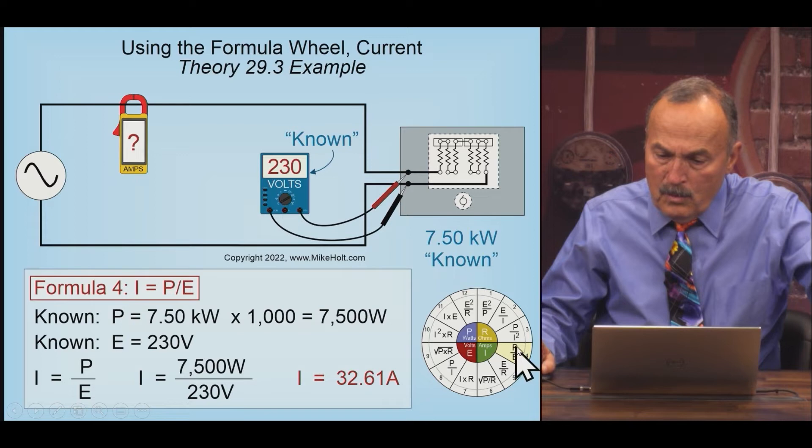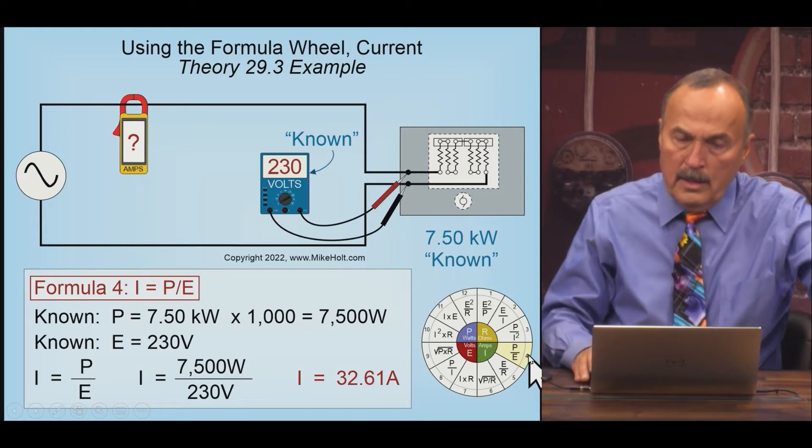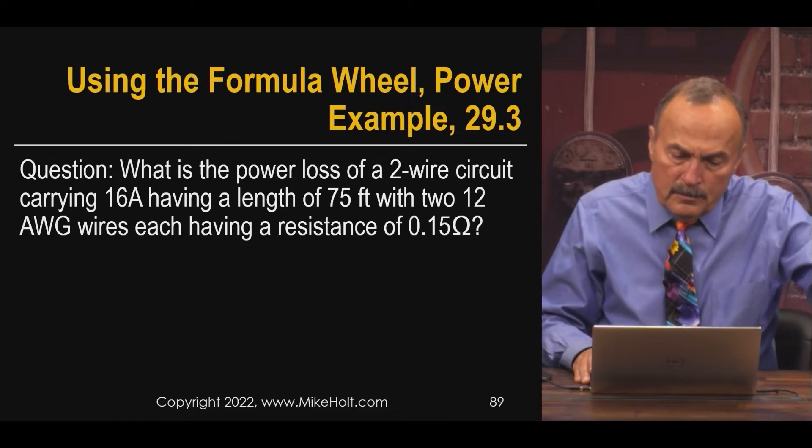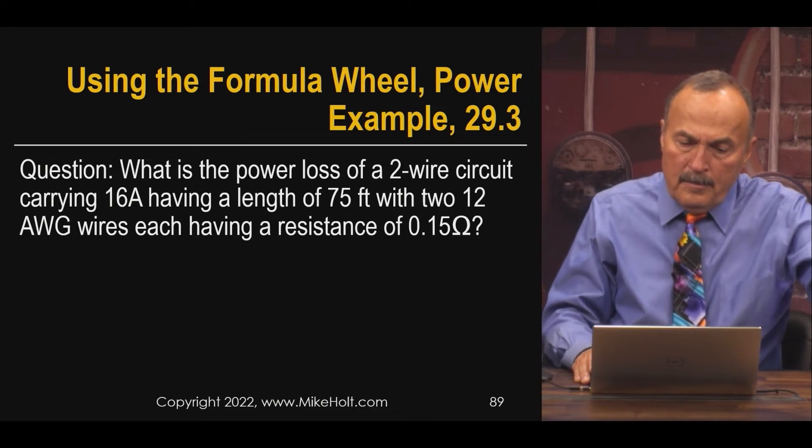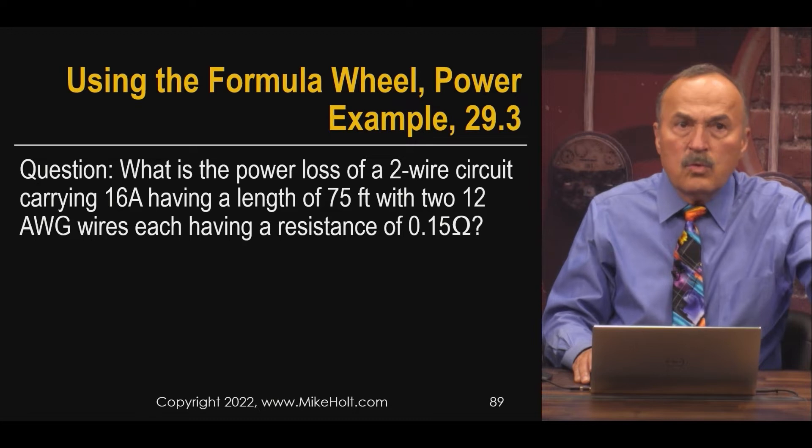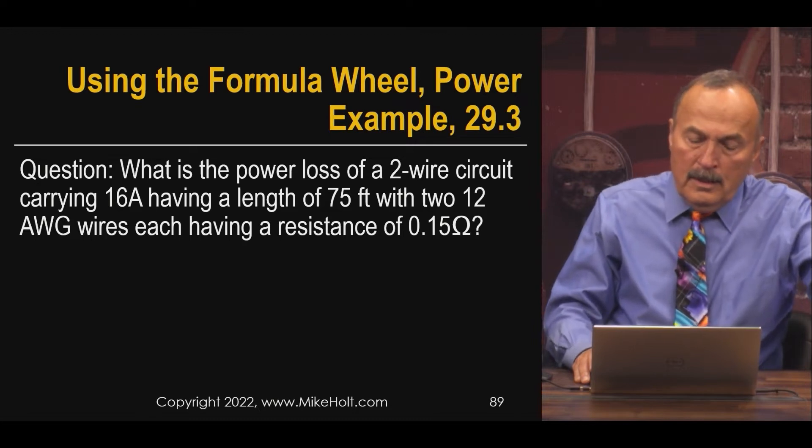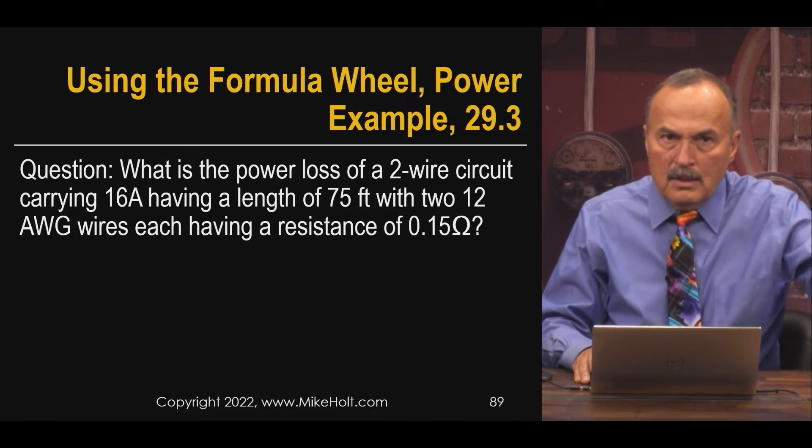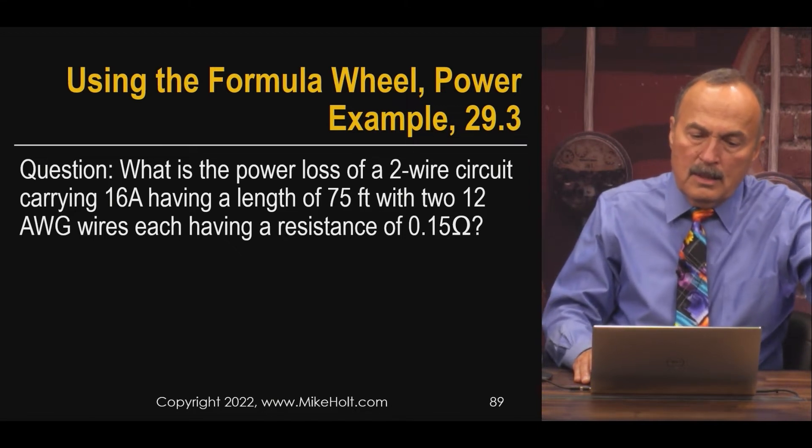What about if you ran two wires and it carries 16 amps, and it's 75 feet of 12 gauge wire, and that wire has a resistance of 0.15 ohms each? Just so we're not having you go to Chapter Nine, Table 8, Table 9.